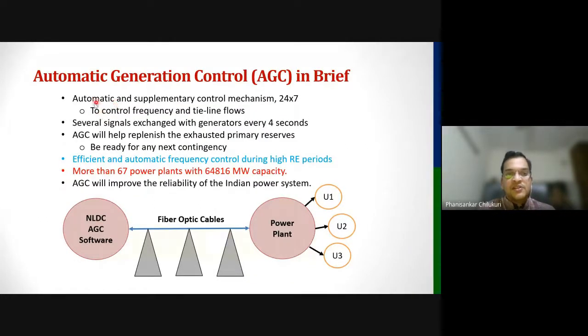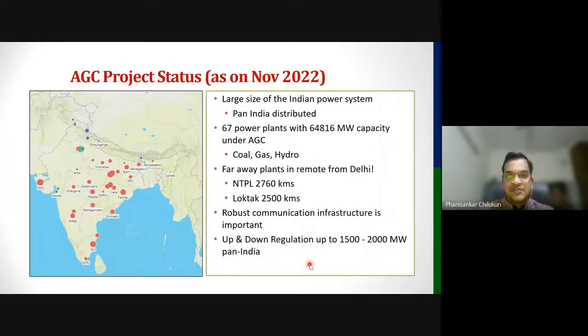So briefly, what is automatic generation control? This is an automatic supplementary control mechanism, 24 by 7, to control frequency and tie line flows. Several signals are exchanged between the NLDC and the power plant every 4 seconds. AGC will help replenish the exhausted primary reserves so that we are ready for the next contingency. It's an efficient and automatic frequency control during high RE periods. More than 67 power plants are under AGC as of now, with 65 gigawatt capacity. It is aimed to improve the reliability of the power system.